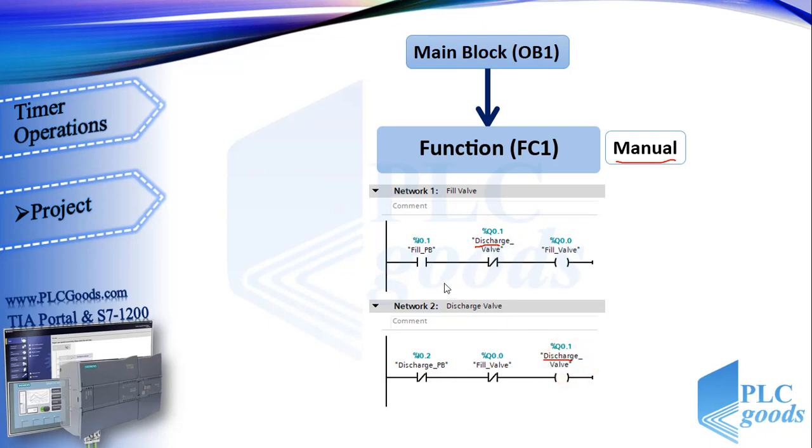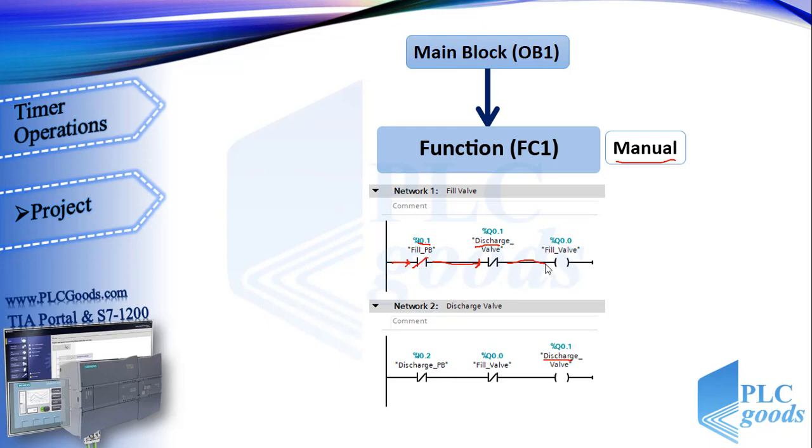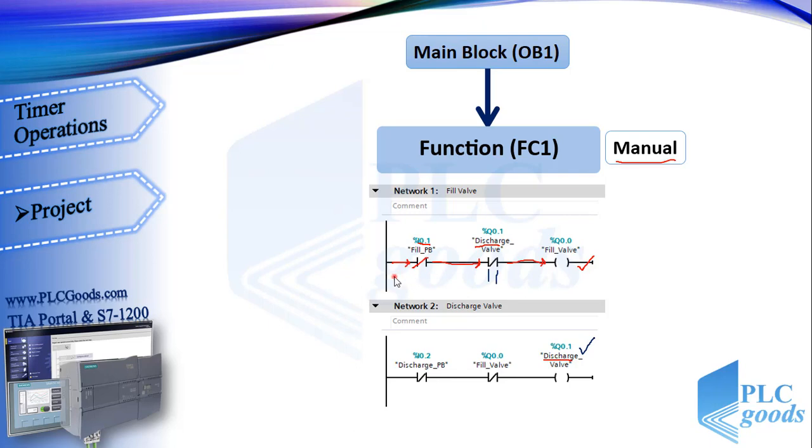Let's see how this program works. When fill push button is pressed, the virtual power reaches to this contact. If the discharge valve is off, this contact will pass the virtual power. So the fill valve will change to on. But if the discharge valve is on, it makes this contact change to open, so the virtual power won't reach to fill valve.